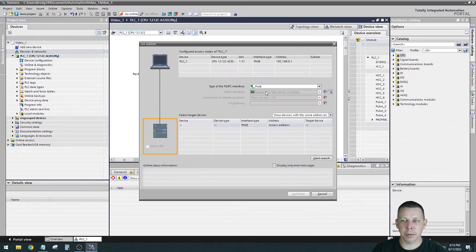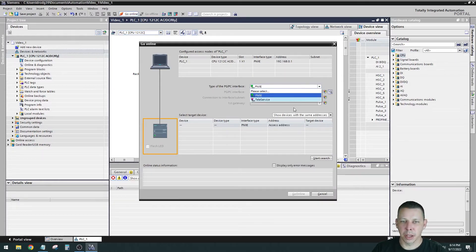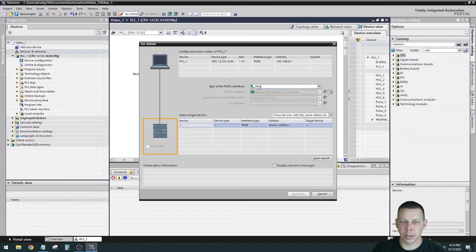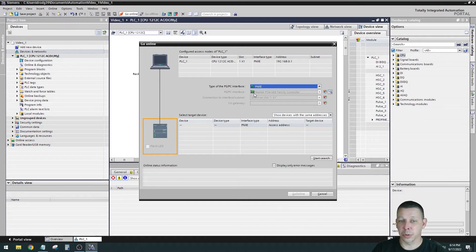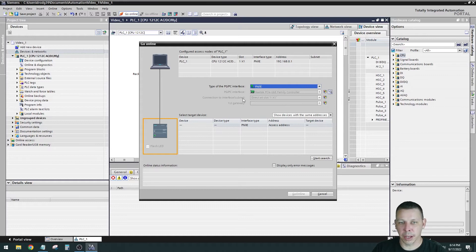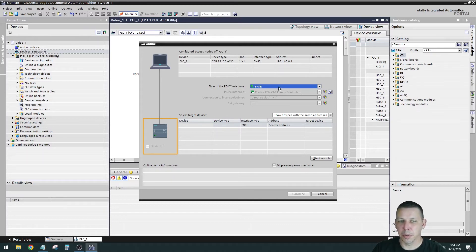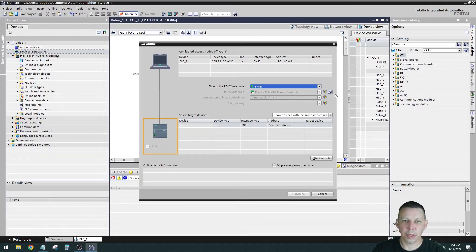This might be set up slightly different than what you're going to see, but it'll be all the same screens. Type of interface, you're going to click PN/IE. You'll probably have a pull down here on the next one to select which controller you want to use. You want to use the one that is the hardwired ethernet card in your computer. Don't select Bluetooth, don't select Wi-Fi. I only have one ethernet controller in my computer so I don't get to choose, but you'll probably have a list. Select the one that's not wireless, the one that you're actually connecting the processor to via ethernet cable.